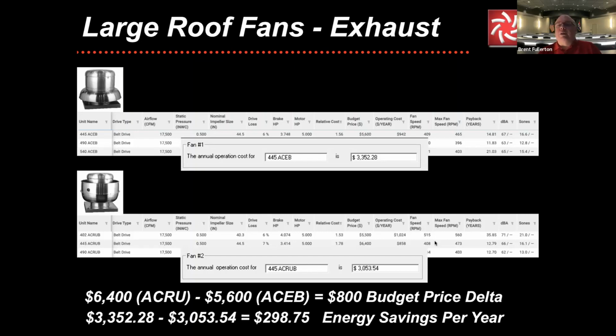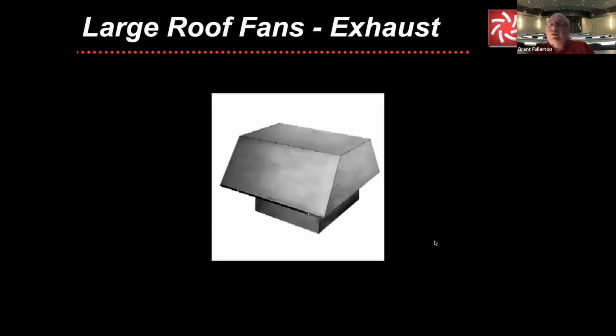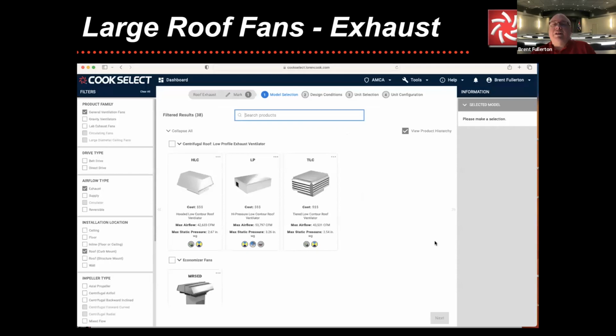I have some design build contractors. I have some consulting firms across my entire region that they always go immediately to the first style fan up on the left. I've got some that'll always go to the lower one. And I've got some that have a mixture of different styles of product. So let's continue this. What's this one? Well, this one has the same interior guts as those two prior ones, but it has a larger hood on it. It does direct the air down. And if it doesn't matter that the air is being directed down, but you have a larger hood, it has less pressure. So we're going to run that selection back through that exact same CFM and static pressure.